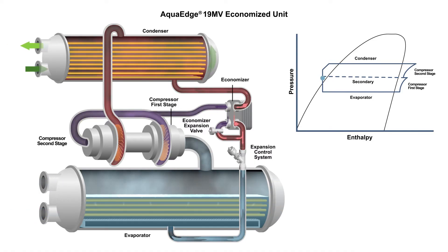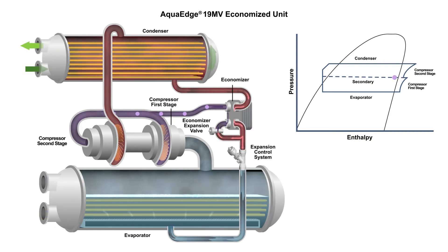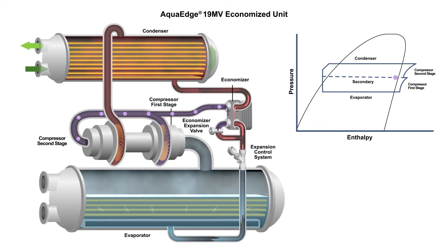Simultaneously, primary liquid flow continues through the expansion control system to become a low-pressure liquid, which enters the evaporator to complete the cycle. The intermediate pressure secondary flow vapor returns to the compressor second stage. Since the vapor only travels through half of the compression cycle, this work requires less energy input and improves the efficiency of the entire system.